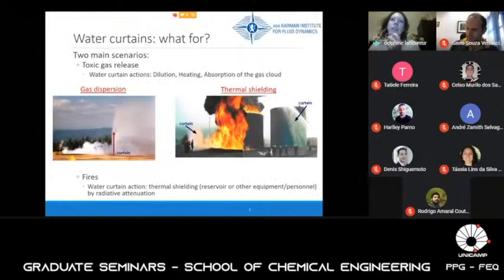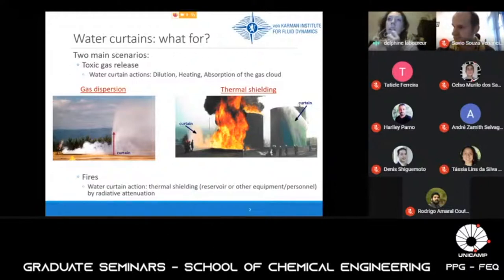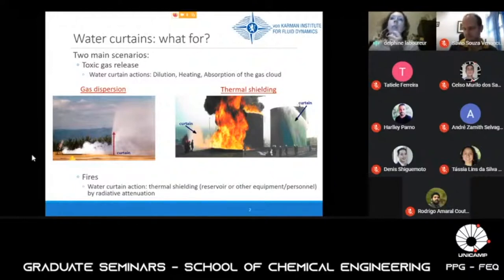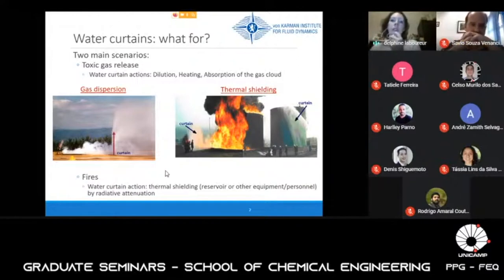Water curtains — what for? They can be used for mitigating two main scenarios. The first one is a toxic gas release: the water curtain will dilute the gas, heating it in the case of cold gases like LNG or methane, but also absorb the gas if it is soluble in water. Water curtains can also be used as thermal shielding to protect reservoirs, other equipment, or even personnel from fire by radiative attenuation.